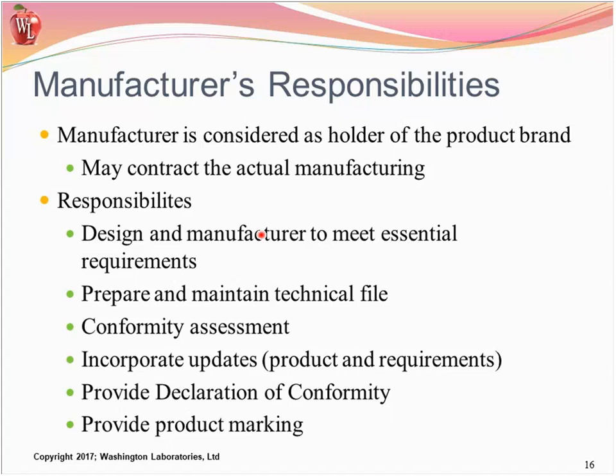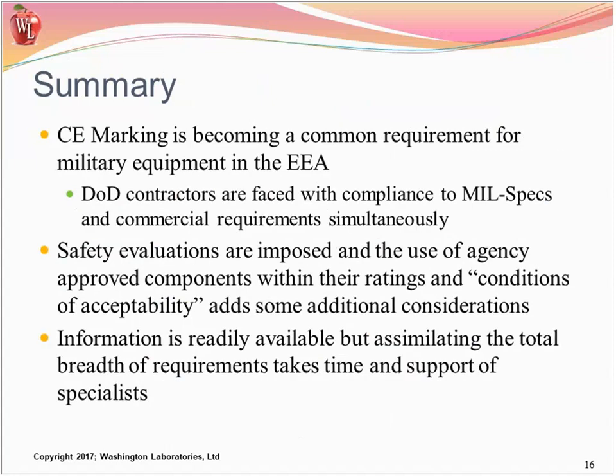Responsibilities include designing manufacture to meet your essential requirements. What are the essential requirements? The things it must do to be considered safe, to meet its required operation, and to remain safe, compliant with various standards, etc. You need to prepare and maintain a technical file. You are the product brand holder. Conformity assessment: arrange to get that evaluation done or do it yourself, and incorporate any updates. Keep up with your applicable files. Provide the declaration of conformity and provide for product marking. You need to have all of these things per the directives; the specific directive requirements are identified there.